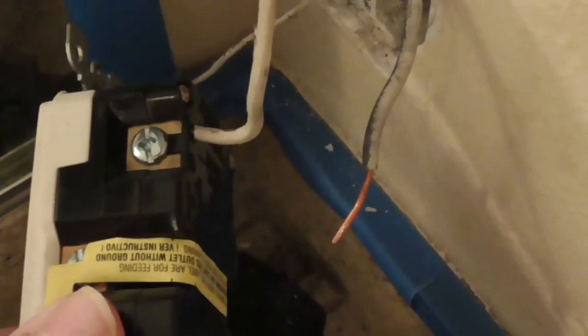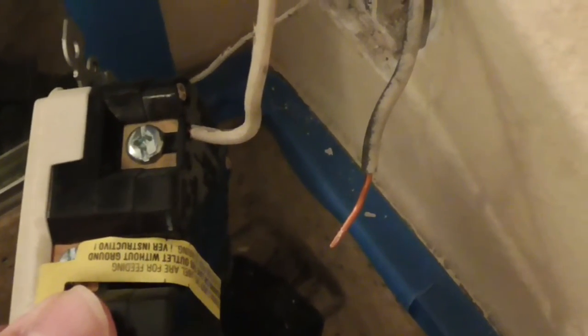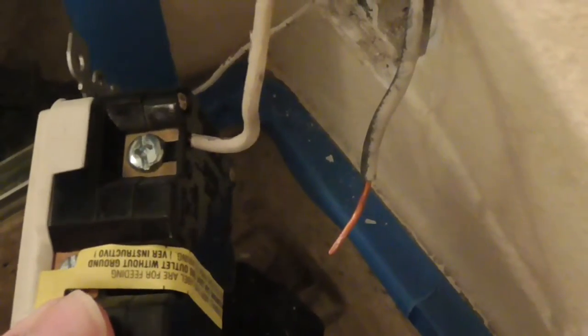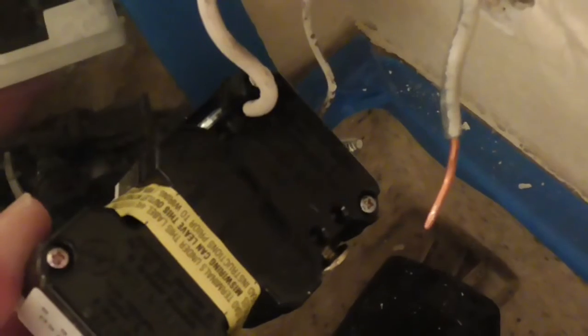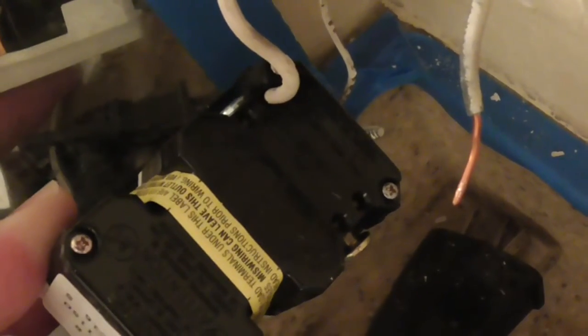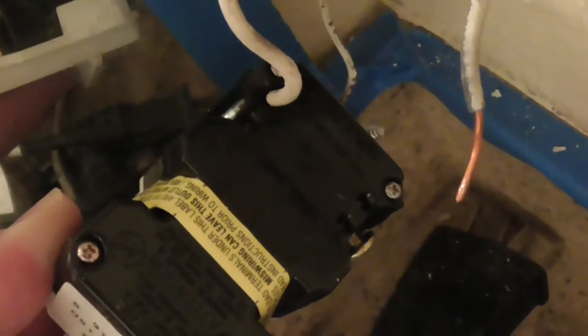One of the wires is done. If you look on this, you can see the wire can go on the screw, and the wire can also go, see these little holes in there, see the hole where the wire is going in, there's two holes. So, some of these, you have a little tab that you have to put a screwdriver in, a flat blade, and then it will release the tab, or you push the wire in, the wire will go in and it will lock. To remove it you have to put a flat blade screwdriver in there, press inward, and the wire will come out.